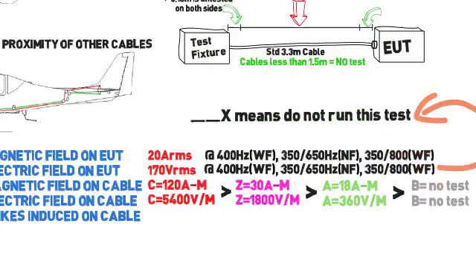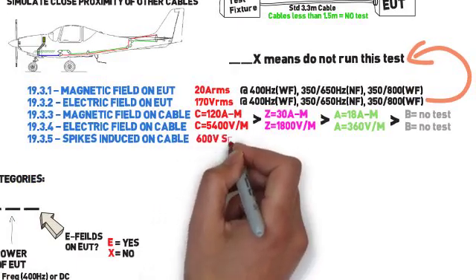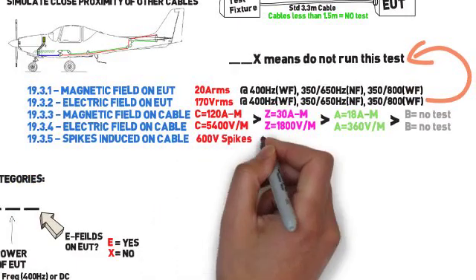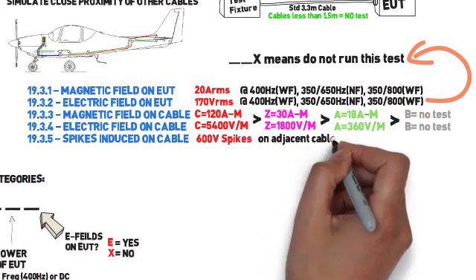Last but not least, spikes induced on the interconnecting cable has a test level of 600 volts. This spike is induced on an adjacent cable and not the EUT cable. Okay, let's go over how to run these fairly primitive tests.